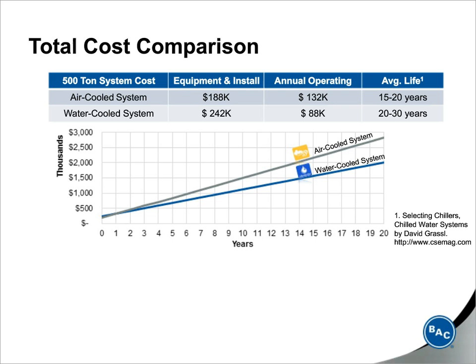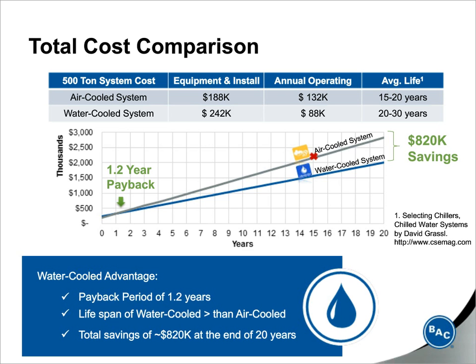So a water-cooled system may initially cost $54,000 more than an air-cooled system, but it actually can last twice as long as the lifespan of an air-cooled system. Now, the water-cooled system can offer a payback in just over 1 year. And over a 20-year period, a water-cooled system saves more than $800,000 over an air-cooled system. Okay? For this building system, a water-cooled system really shows a clear advantage in total cost of ownership over an air-cooled system.